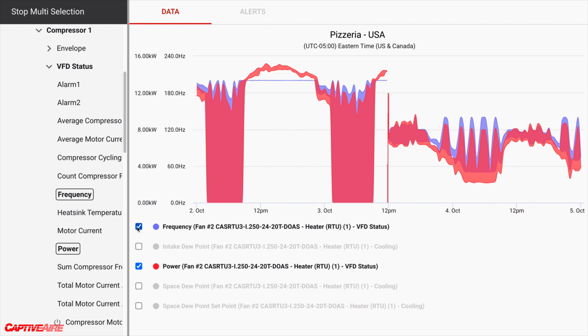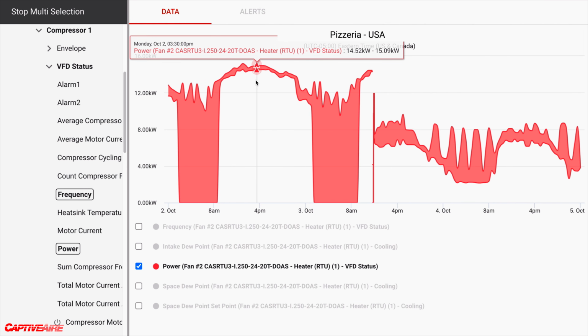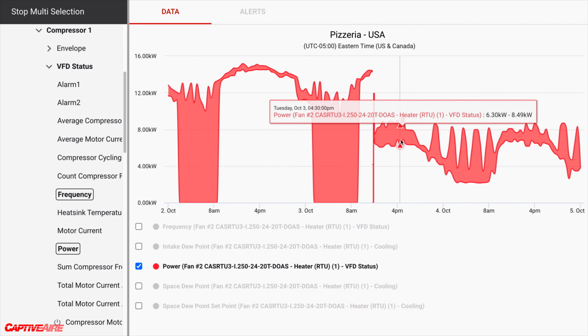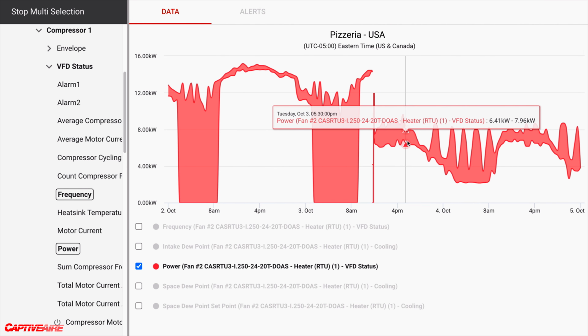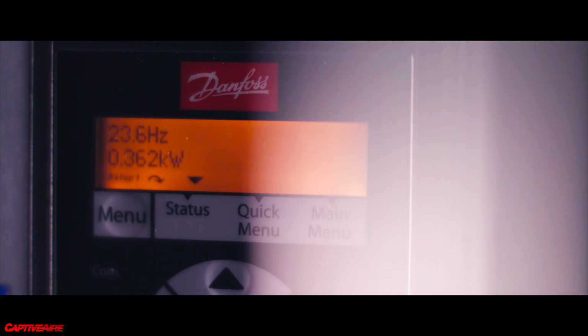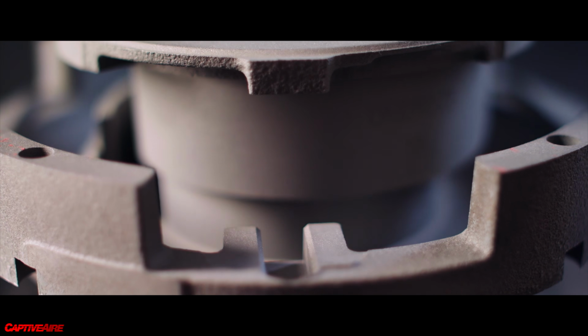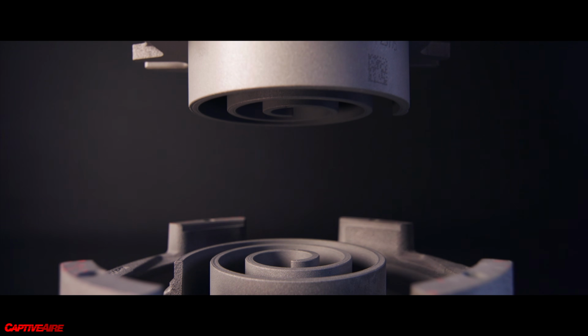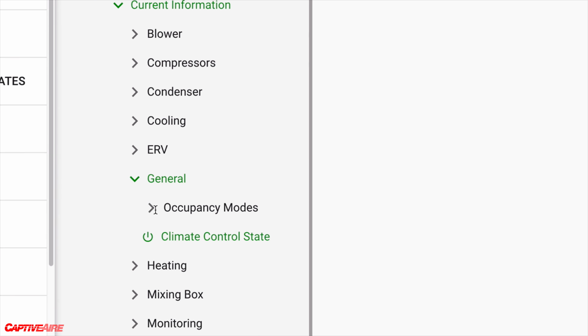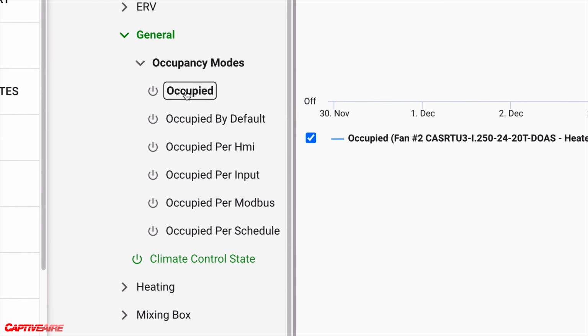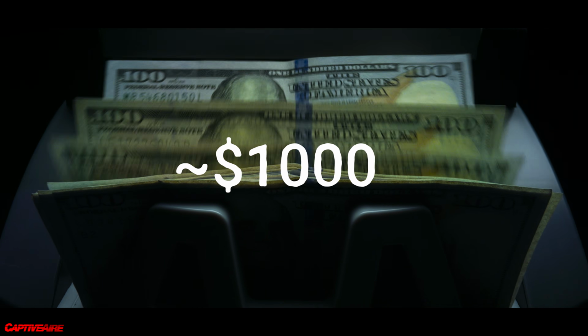Before adjustments were made, we were seeing power usage around 13 to 16 kilowatts. And after, we're averaging about 6 to 8 kilowatts. You pay your electric bill based on kilowatt hour usage. So in this case, we can say we cut the compressor's energy usage by almost half, which is a huge deal because the compressor is the biggest power draw of the entire system. When you put this together with the findings about occupancy scheduling, we estimate that the total savings for this user using our recommendations is upwards of $1,000 a month.